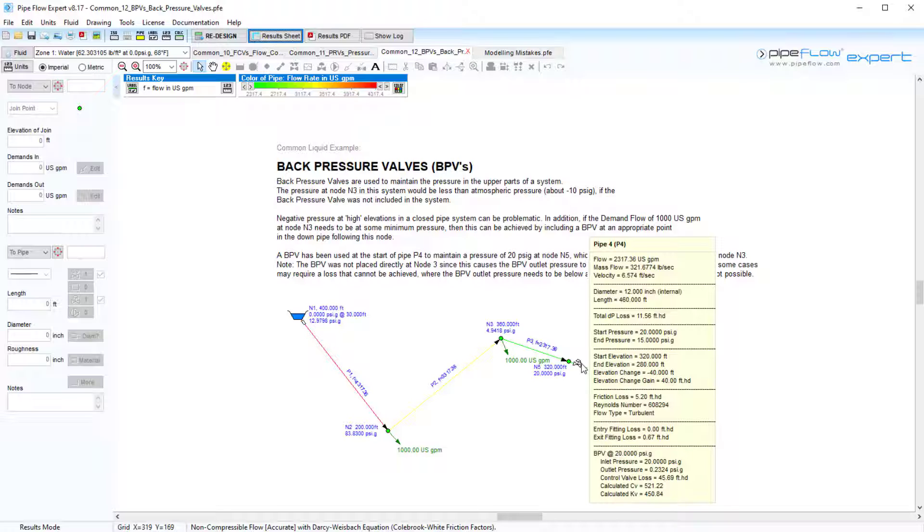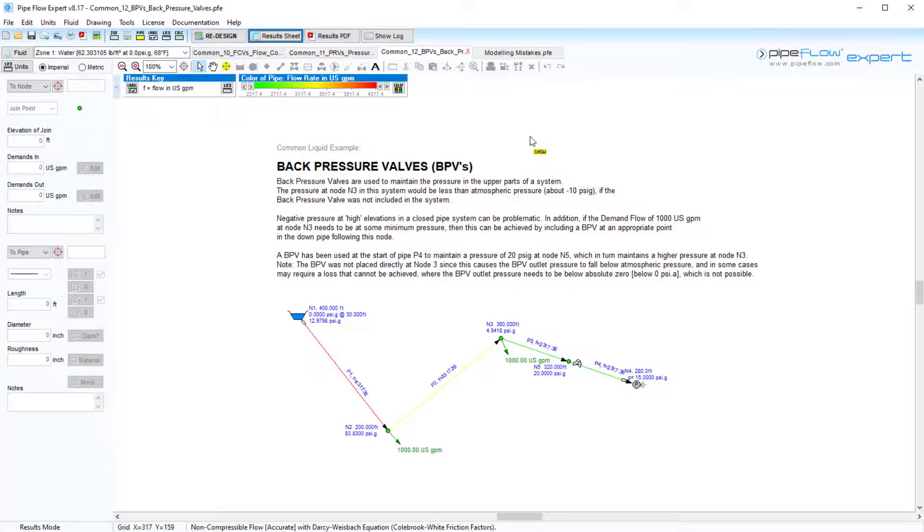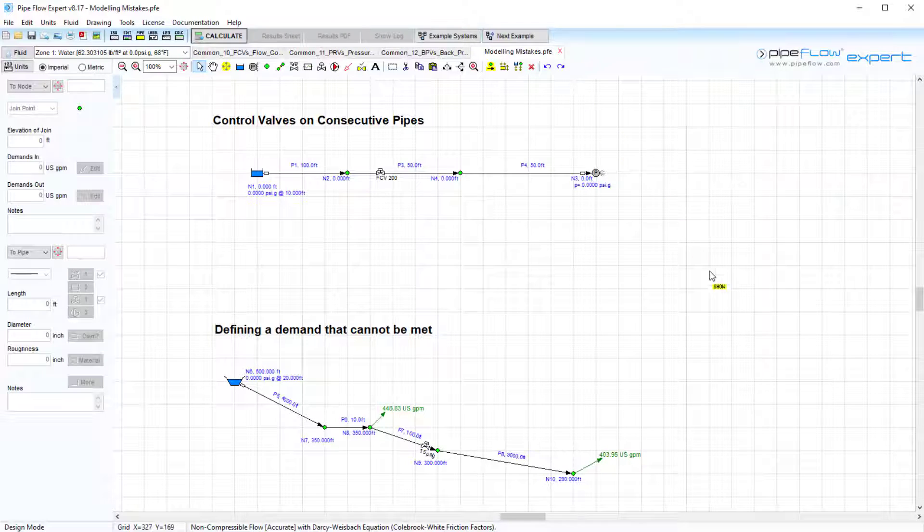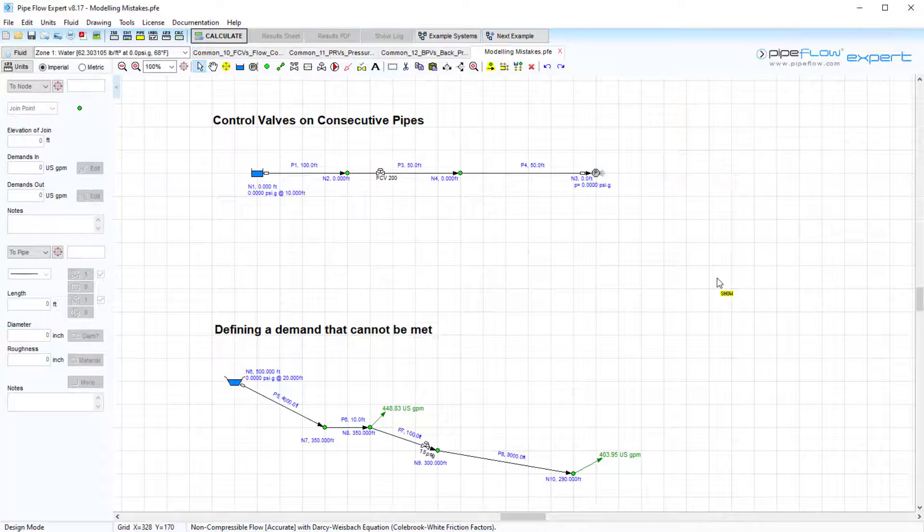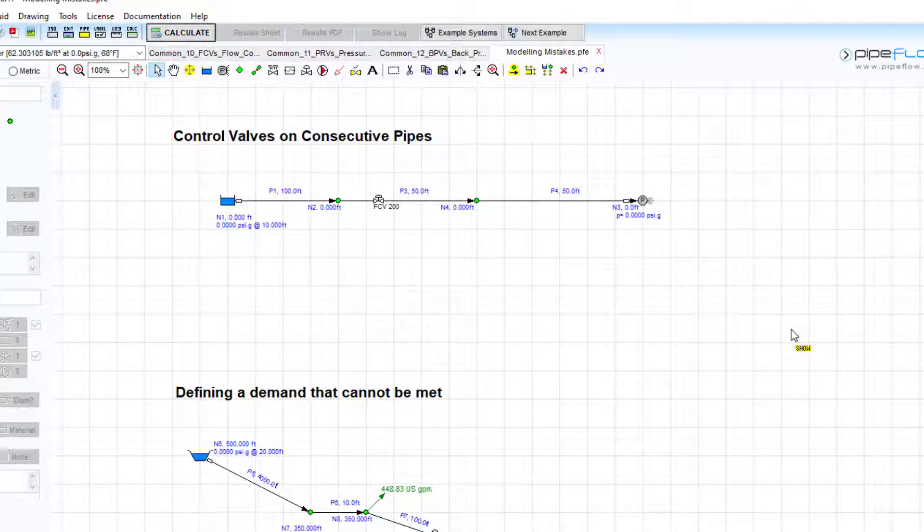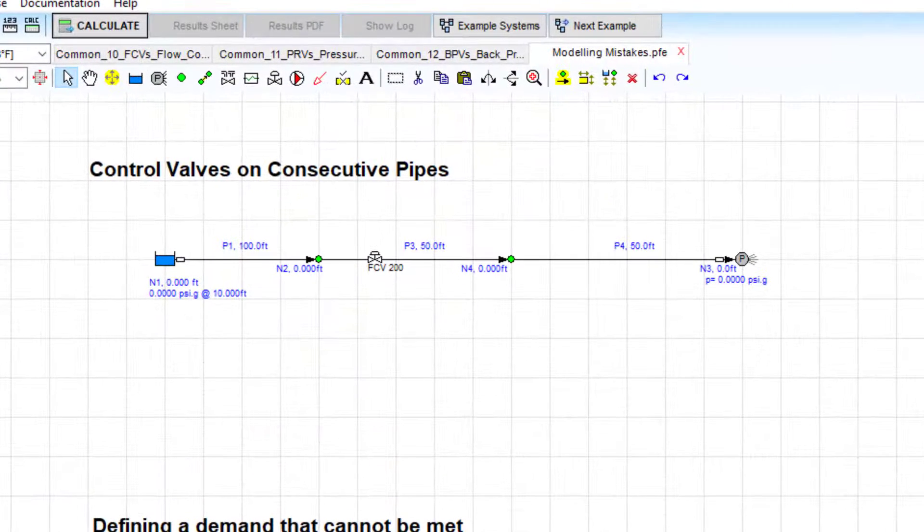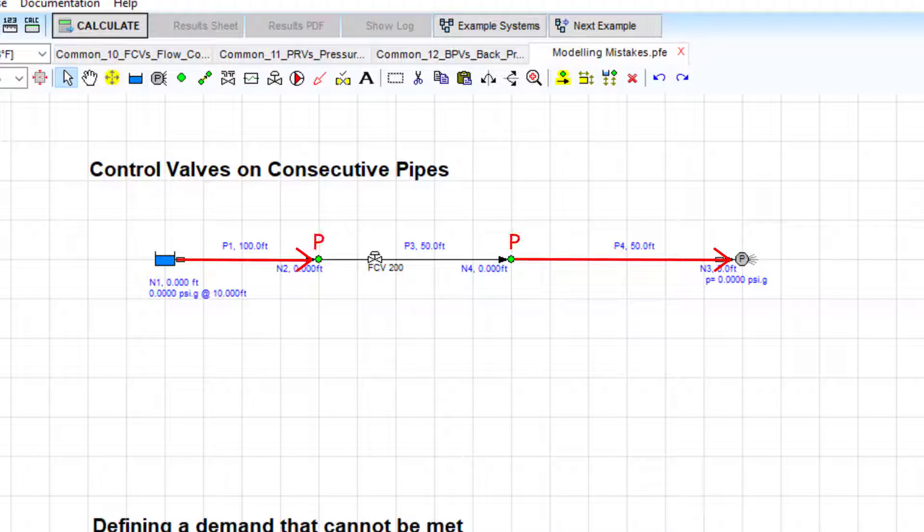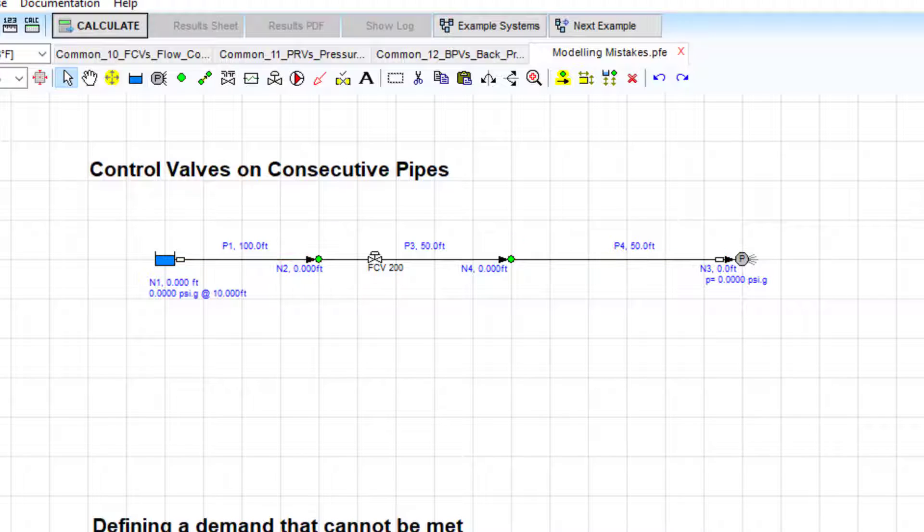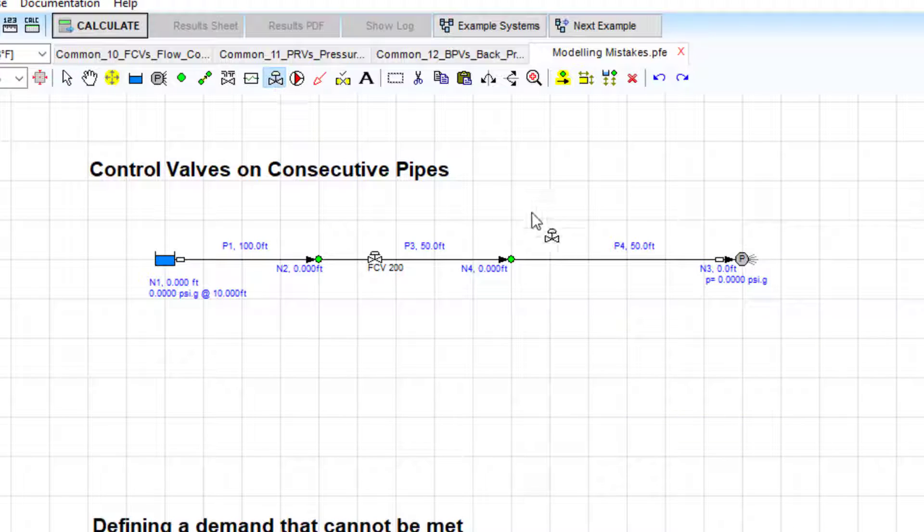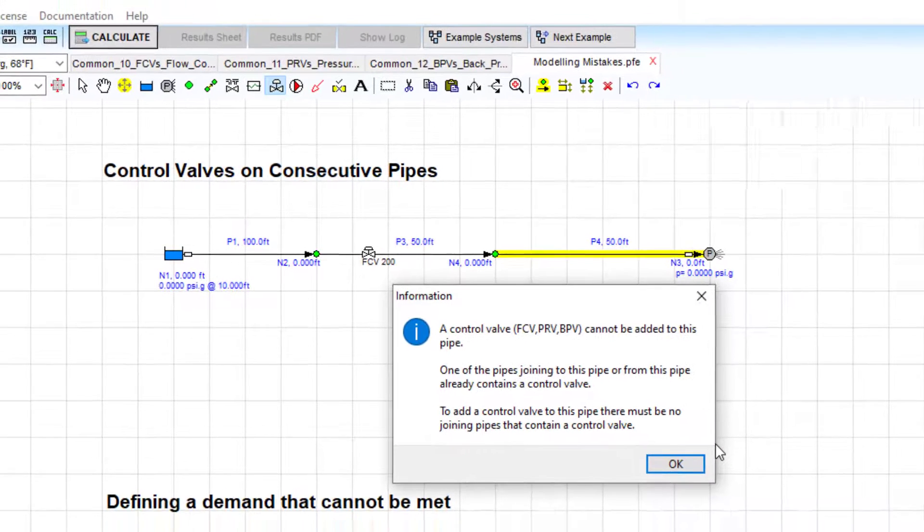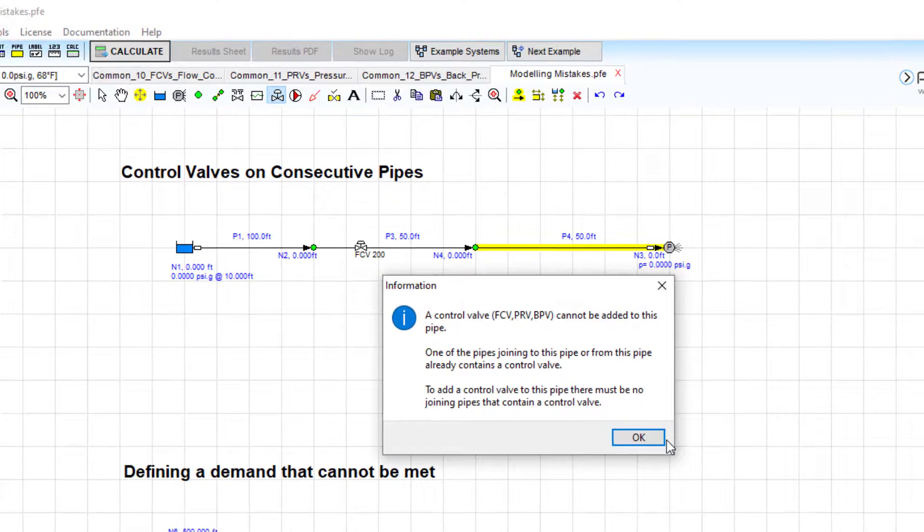In this video, we also wanted to discuss some common modeling mistakes when using Pipe Flow Expert. The modeling of flow control valves, pressure reducing valves, and back pressure valves requires that the flow rates and pressures from adjacent pipes must be used as a reference to establish the pressure loss that the control valves must introduce. To allow this, a control valve cannot be added to any pipe where a joining pipe already includes a control valve.